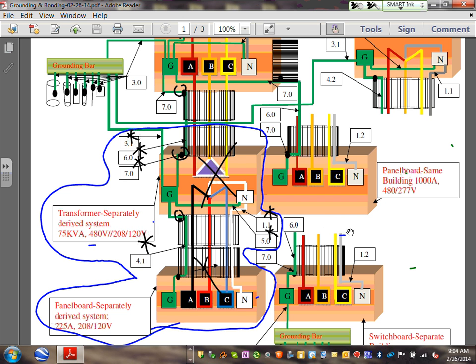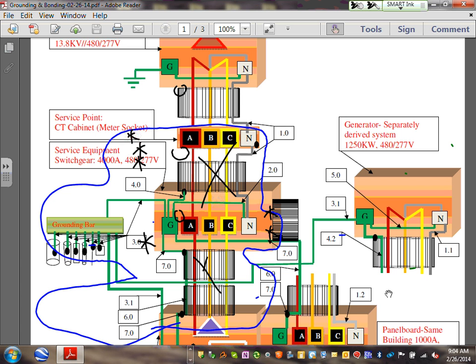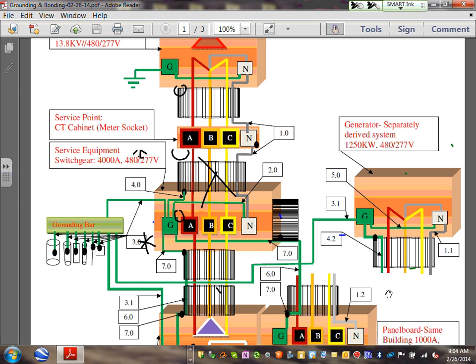All right, last thing. The last thing I'm going to talk about, guys, is generators. Generators you can run as a separately derived system or a non-separately derived system. What is that, Chad? A generator is a source of power. If you switch the neutral when you tie it to your power system, then this is called a separately derived system. If you don't switch the neutral, then it's called a non-separately derived system.